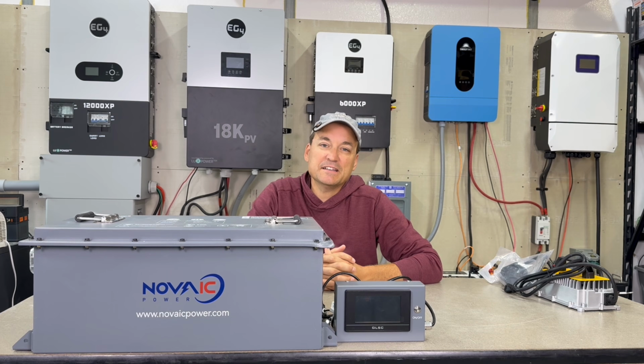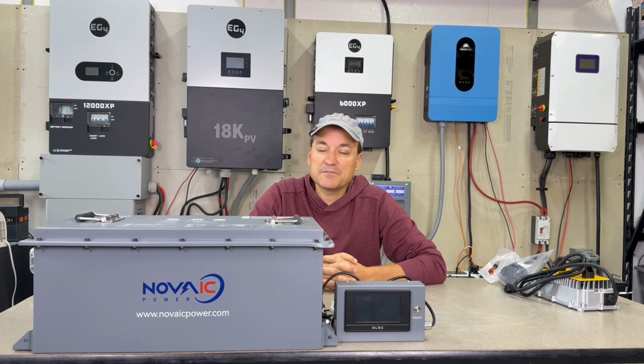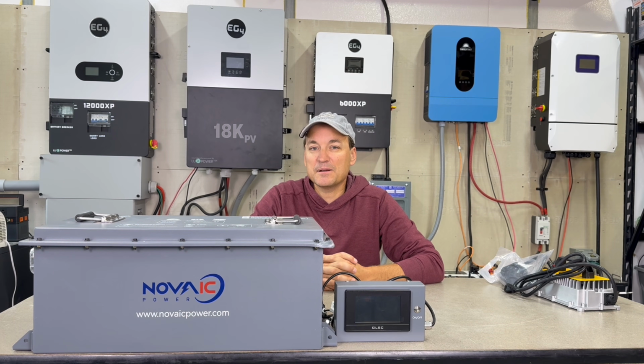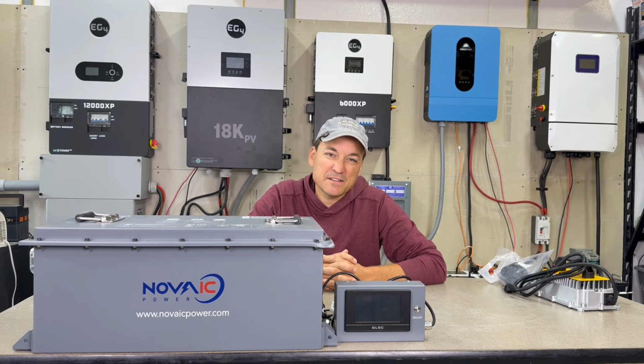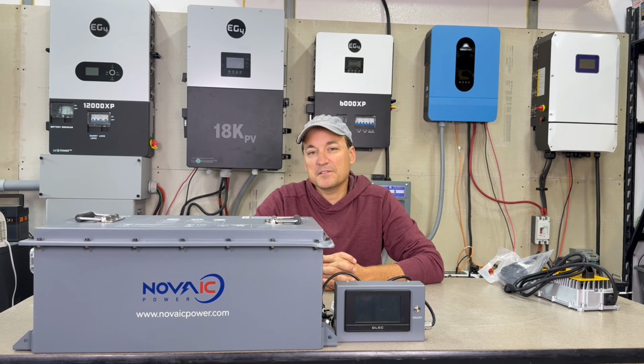So technically you can discharge lower than 32 degrees, but if you want to charge, lithium iron phosphate can be damaged if it's 32 and below. So that's what the heaters are for.